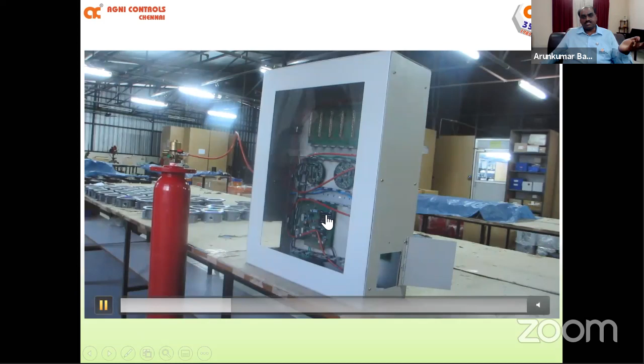Since it's in entire discharge mode, the carbon dioxide is still being discharged. As I said in the basics of fire, once we introduce carbon dioxide into the fire, it does two things: removes oxygen and gives a cooling effect. In this cabinet, the oxygen content would have fallen to around 16% or 17%, and icing has slightly formed, meaning the temperature has also come down inside this cabinet.